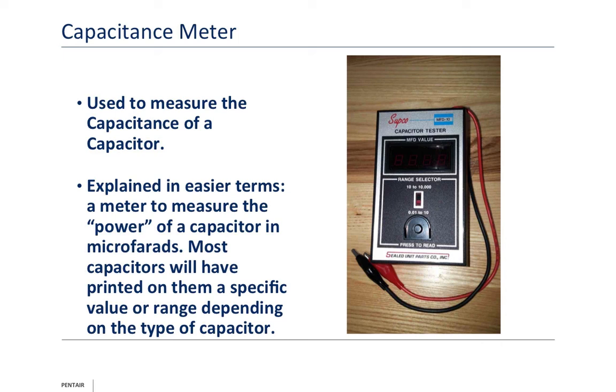And here's a tip. If you notice that capacitors are blowing out or getting weakened and you're often replacing them, remember that capacitors are rated in microfarads, but they're also rated for voltage. For example, you might have one rated 86 microfarad plus 20 minus 0 at 370 volts, and we keep having to replace that capacitor every 2 years or so, or the control box.